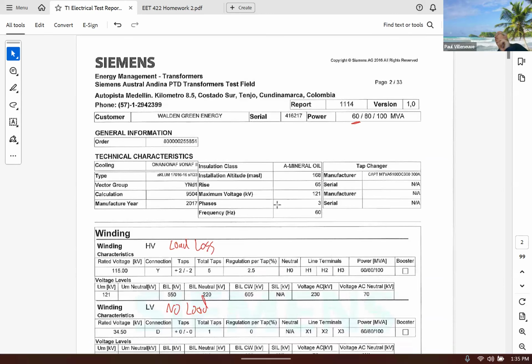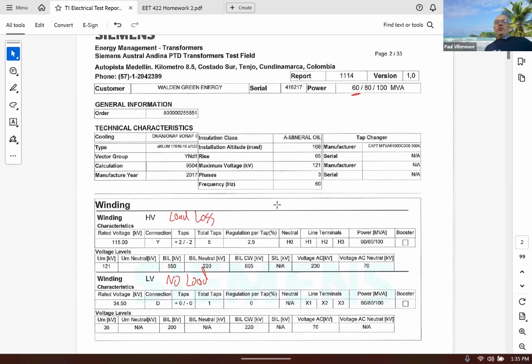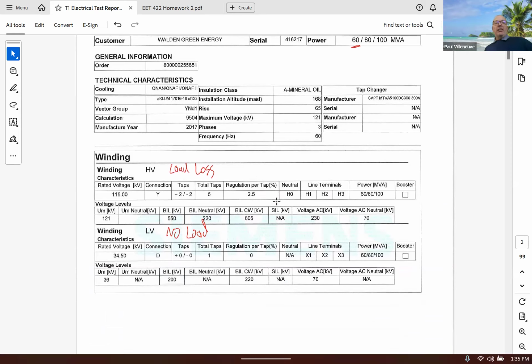With voltages that are line voltages and phase voltages. So be careful when you look at 115 and 34.5, you have to think about whether those are line voltages or phase voltages. And you can tell a little bit, see the connection here? This says it's a Y connection, and that's a delta connection. So this transformer on the high side is connected like this, and on the low side, it's connected like that.